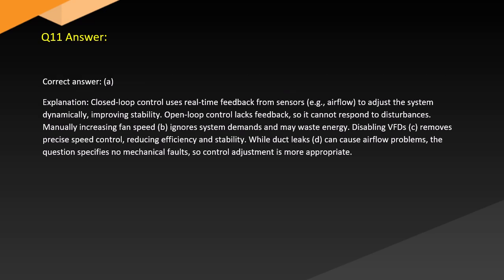Answer. Correct answer: A. Explanation. Closed-loop control uses real-time feedback from sensors, e.g. airflow sensors, to adjust the system dynamically, improving stability. Open-loop control lacks feedback, so it cannot respond to disturbances. Manually increasing fan speed, B, ignores system demands and may waste energy. Disabling VFDs, C, removes precise speed control, reducing efficiency and stability, while duct leaks, D, can cause airflow problems. The question specifies no mechanical faults, so control adjustment is more appropriate.